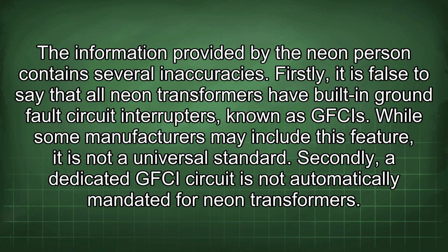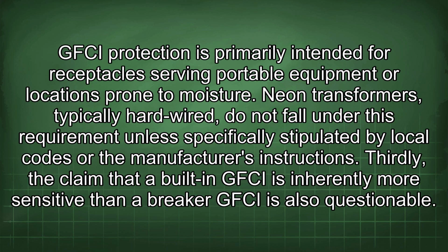Secondly, a dedicated GFCI circuit is not automatically mandated for neon transformers. GFCI protection is primarily intended for receptacles serving portable equipment or locations prone to moisture. Neon transformers, typically hardwired, do not fall under this requirement unless specifically stipulated by local codes or the manufacturer's instructions.